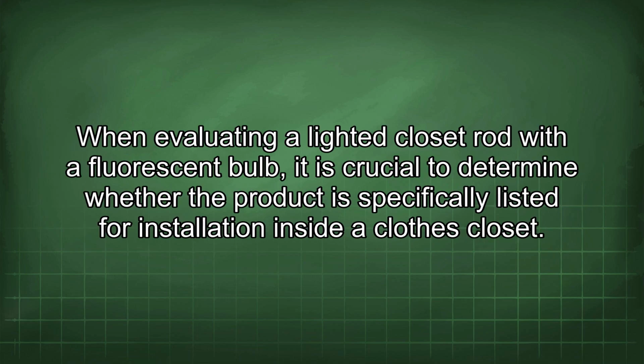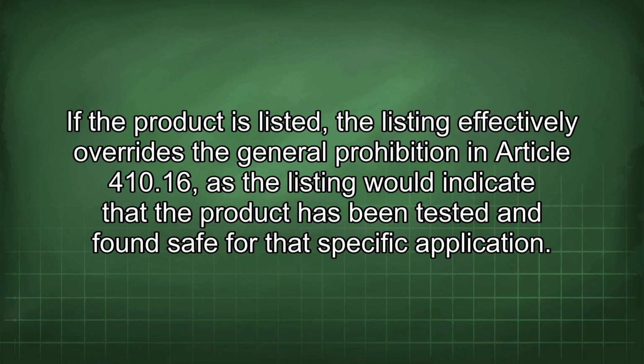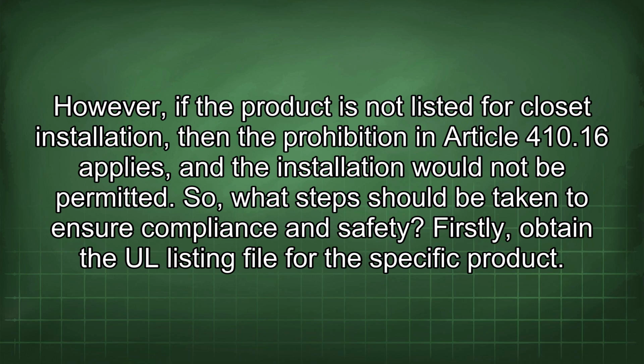When evaluating a lighted closet rod with a fluorescent bulb, it is crucial to determine whether the product is specifically listed for installation inside a clothes closet. If the product is listed, the listing effectively overrides the general prohibition in Article 410.16, as the listing would indicate that the product has been tested and found safe for that specific application. However, if the product is not listed for closet installation, then the prohibition in Article 410.16 applies, and the installation would not be permitted. So, what steps should be taken to ensure compliance and safety?